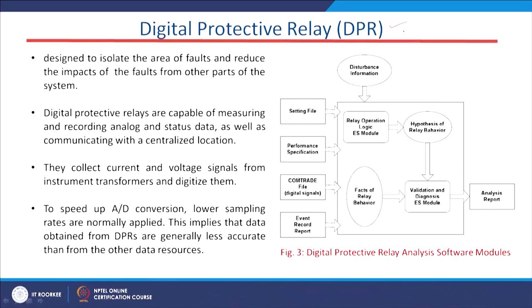Another device is the digital protective relay, which will be discussed more in later classes covering the smart grid protection system. This relay makes decisions to protect every equipment — generators, transformers, transmission lines, feeders, and loads. Each piece of equipment is protected by one digital relay. The relay takes voltage and current information, applies signal processing techniques, and gives a trip signal to the circuit breaker.